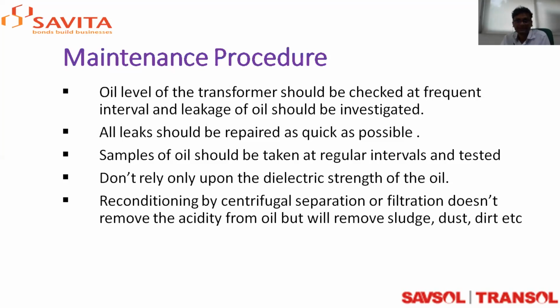Samples of the oil should be taken at regular intervals and tested. Sample testing is always a job where you have to spend money. Sometimes people think, why spend money on testing samples? But when you get the report, there is always a tendency to say, okay, the report is in the file, it is fine. But one has to interpret these values against the earlier values, collect the data, and on the basis of that data you can discuss with experts. You can really interpret those things in terms of the life of the transformer. One can easily guess what will happen tomorrow with the transformer.